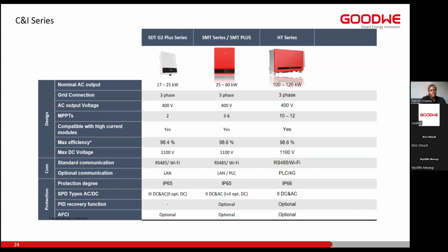Yes, and the PID recovery option for the bigger rated inverters, that is the SMT and the HT series. PID recovery, I will expand on this later on in the upcoming slides. I did mention we have the arc-fault circuit interrupter, AFCI, optional if you want to increase the level of protection of your PV system in terms of localities prone to lightning occurrences or loose connections of your MC4 connectors.